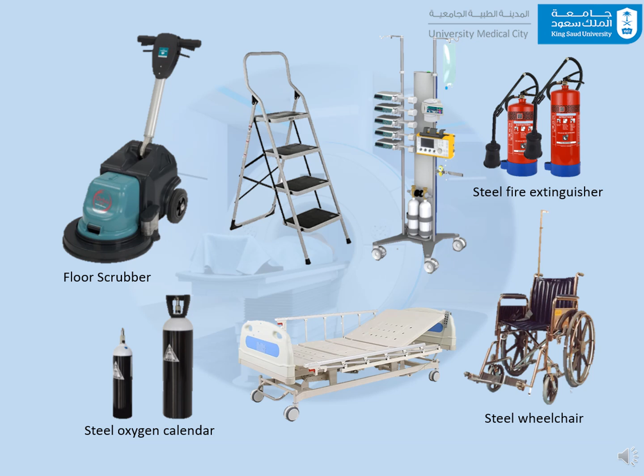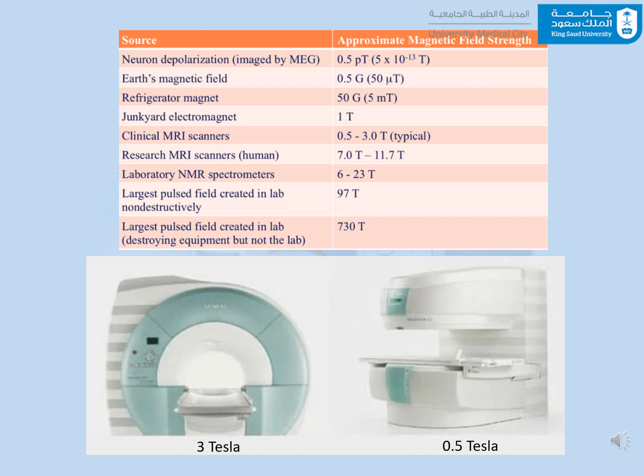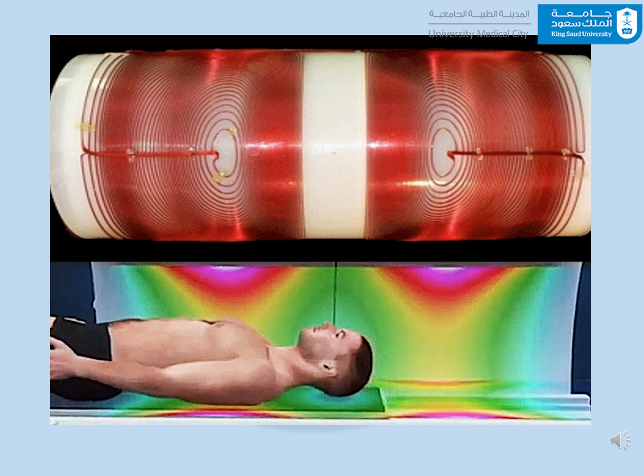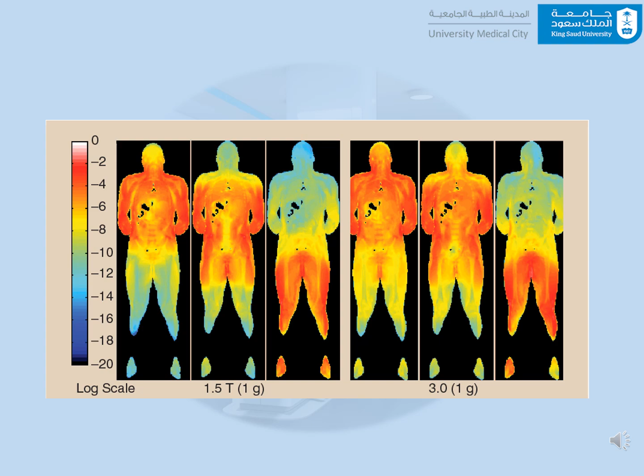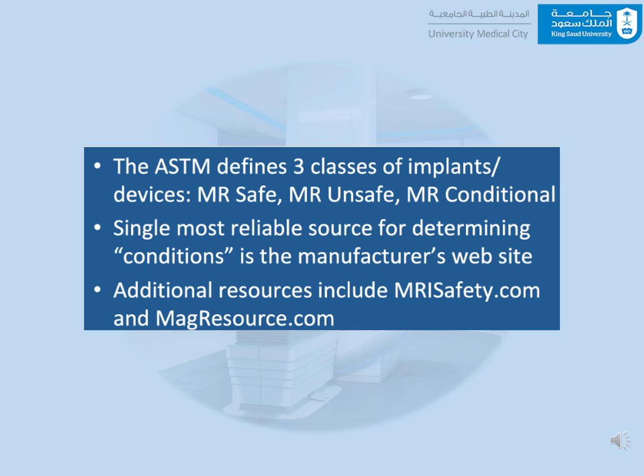MR conditional objects are those that have been shown to pose no known hazards in a specific MRI environment, as long as certain conditions of use are met. The field conditions that define the specified MRI environment include magnetic field strength, spatial gradient of the magnetic field, time rate of change of the magnetic field, radio frequency fields, and specific absorption rate. In addition to these environmental factors, there may be other specific configurations or requirements for the MR conditional item itself that must be adhered to in order to ensure safety within the MRI setting.